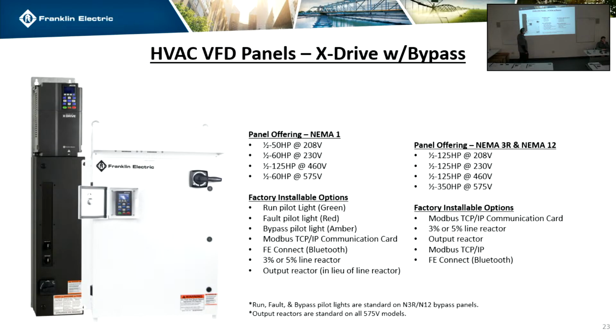So this is the same kind of thing with the bypass attached to it. A more limited range and a little bit limited on the options because of so much stuff that comes in there, but the one addition is the bypass light will be amber. All the other stuff is the same. Yeah, same thing on this slide too. The NEMA ones come with the 5% line reactor, the Bluetooth card. The 460 rating actually is 100 horsepower, not 125. We recently came into an issue where the NEMA 1 enclosure wouldn't fit the largest 125 horsepower drive, so we had to knock that down to 100. But everything else on here is going to be accurate.